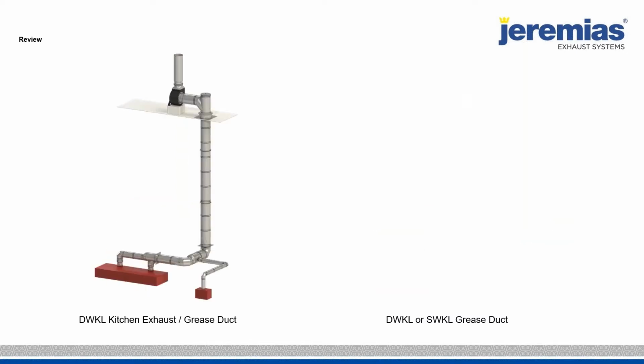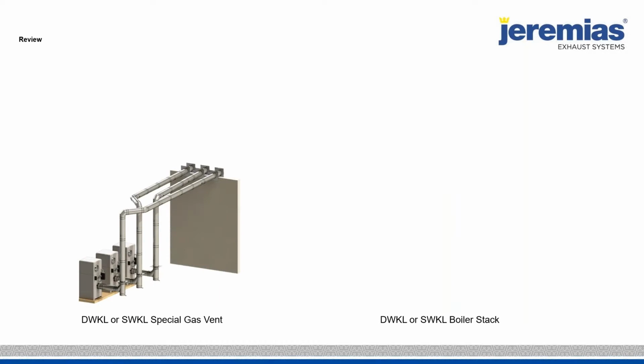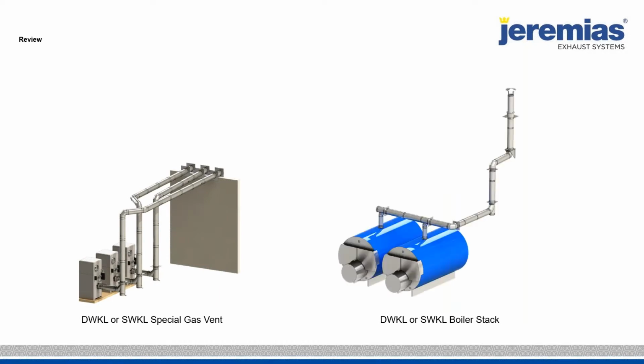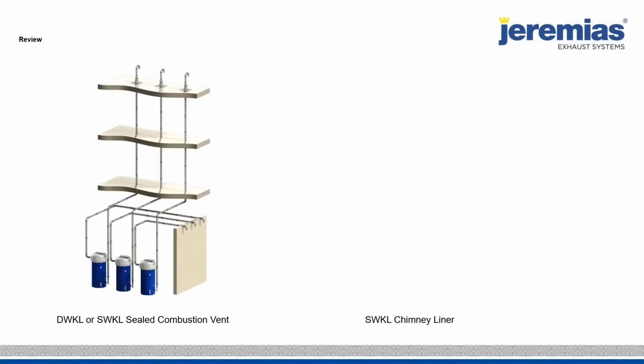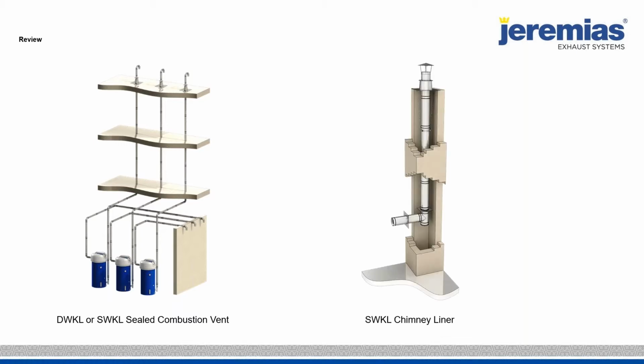Of course, we talked about the kitchen ventilation, maybe a single story application with reduced clearance grease duct. We touched base a little bit on special gas vent. We talked about the boiler stacks, UL 103. We talked about the plastic applications. We're seeing again, our single wall stainless is a viable option cost-wise versus a non-listed, non-warranted plastic.